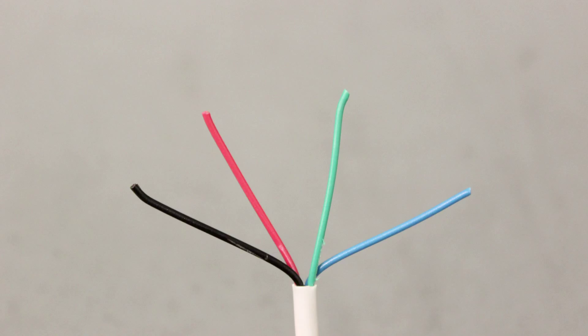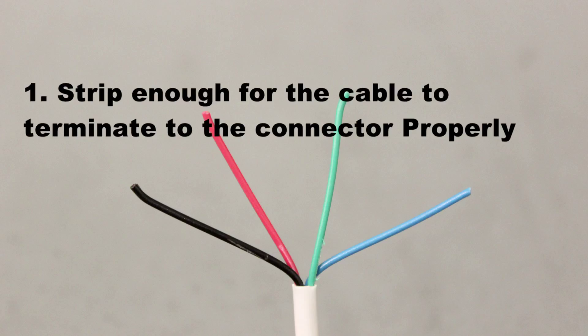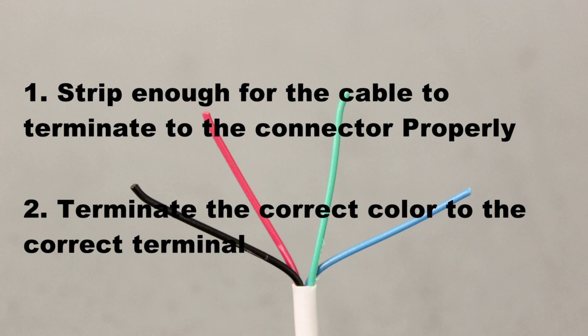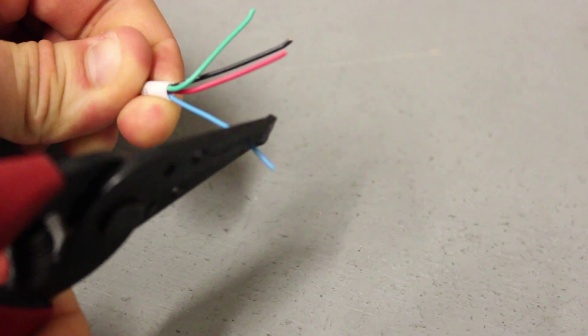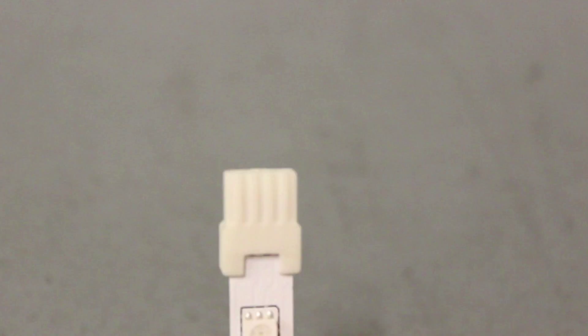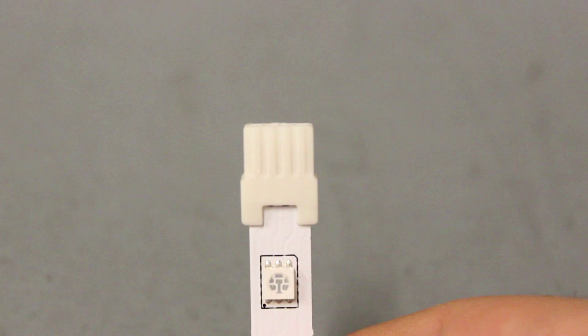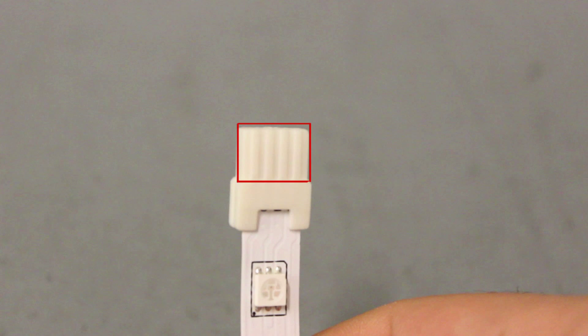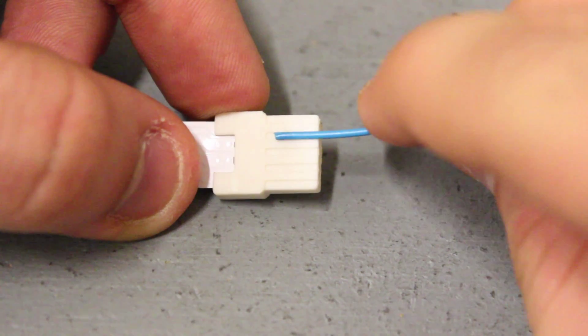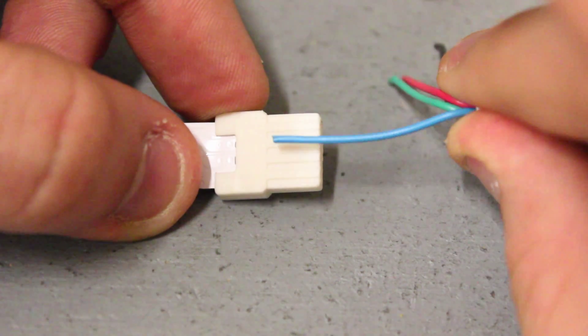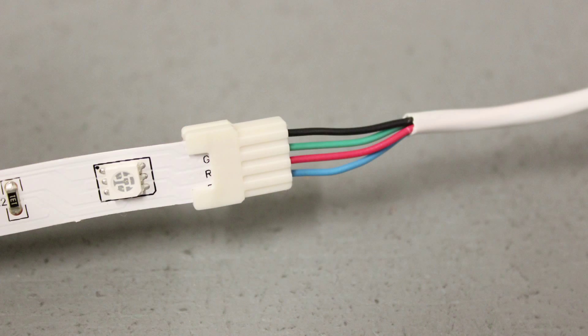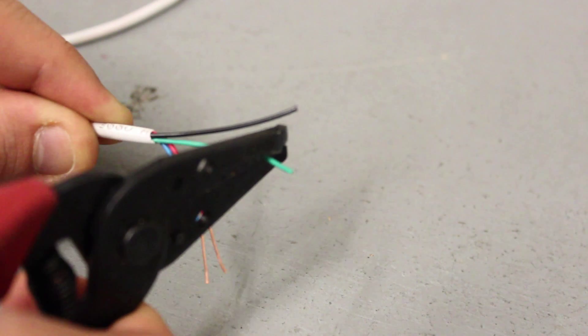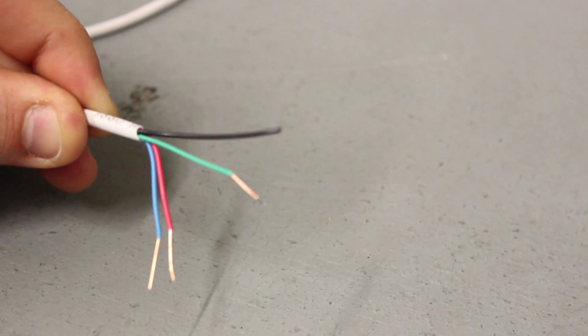Before we strip these wires, we need to make sure that one, we strip enough for the cable to terminate to the connector properly, and two, that we terminate the correct color to the correct terminal. There is an easy way to figure out how much cable you'll need to strip. Take a look at your connector. There is a line on each connector that shows you where the inserted wire is going to stop. You'll need to strip about a quarter of an inch off each lead to ensure that the leads make full contact with each terminal input. Now strip each lead a quarter of an inch using your Klein cable strippers.